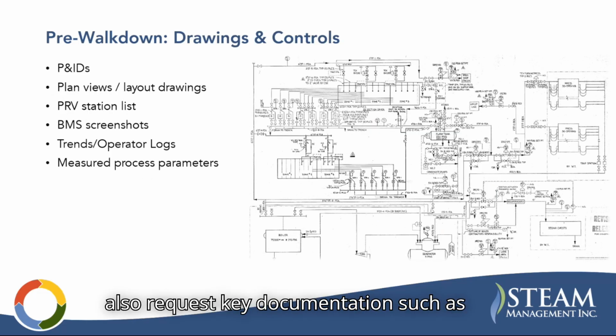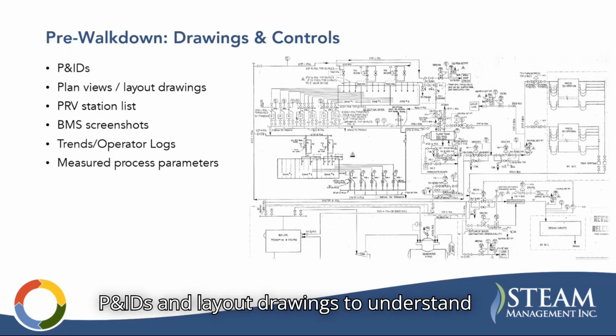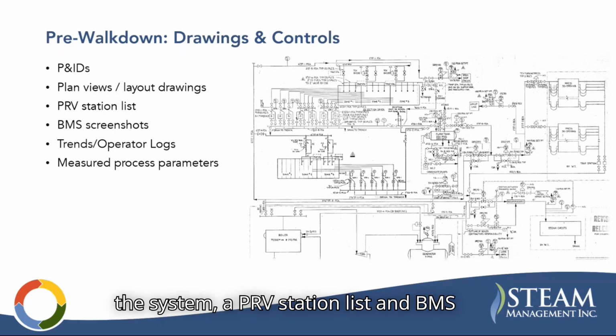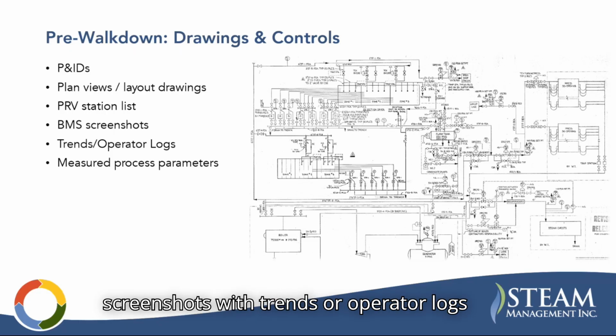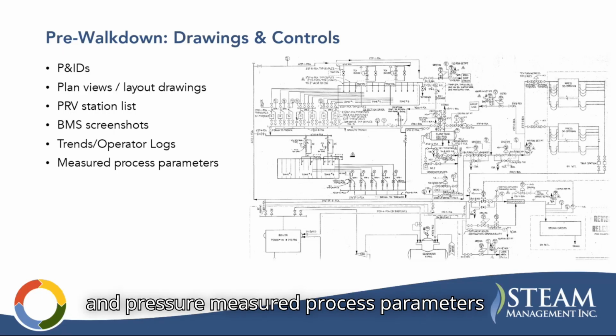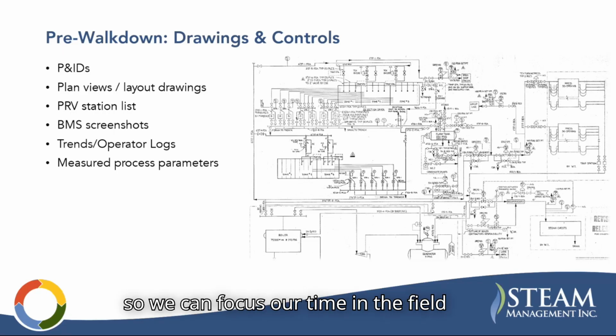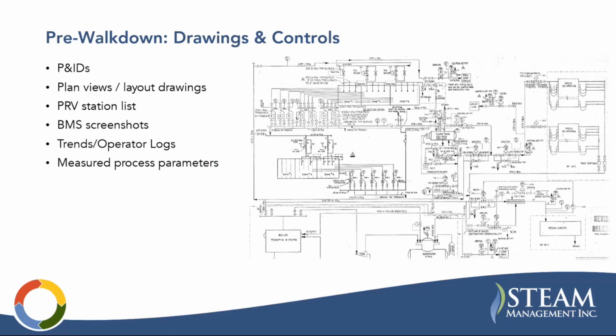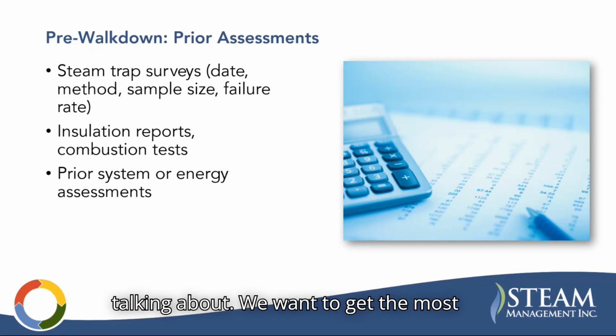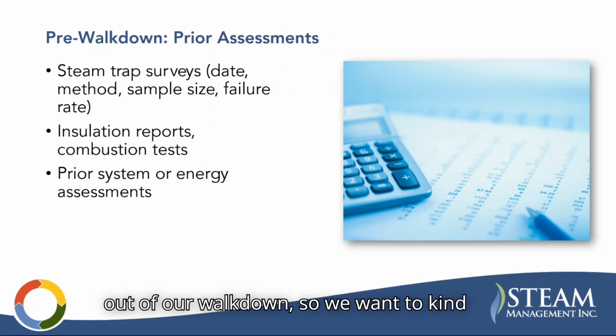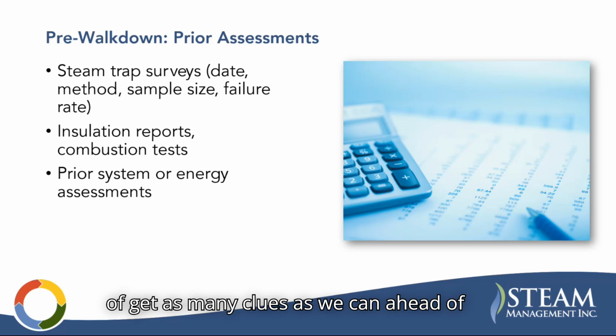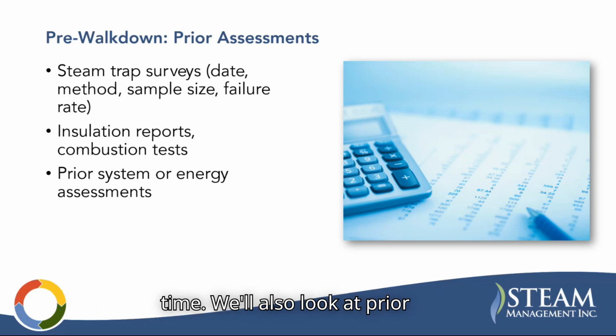We also request key documentation such as P&IDs and layout drawings to understand the system, a PRV station list, and BMS screenshots with trends or operator logs and pressure measured process parameters so we can focus our time in the field where it matters the most. And that's basically what all these are talking about. We want to get the most out of our walk down, so we want to get as many clues as we can ahead of time.